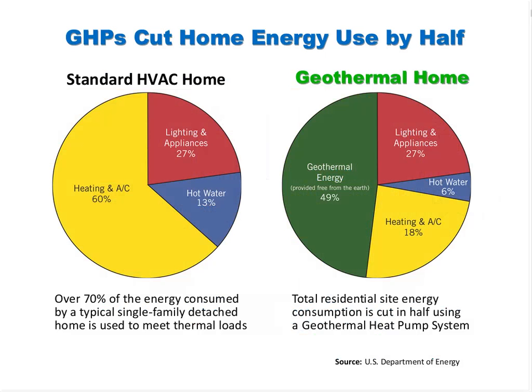And the reason's simple. It's all about ground versus air temperatures. Ground temperatures are a lot more moderate and stable than air temperatures, especially in the summertime. We're all feeling it this summer. Air temperatures can be very volatile and extreme. All you need to do is go onto the roof of a commercial building with black tar and 130, 140 degrees on that roof during the summer, and those air-to-air heat pump systems up there are really struggling to be efficient, whereas if a geothermal system's being used, it's tapping that much more moderate temperature air drawn from the earth, through the water system, through the piping system that hooks into the geothermal heat pump itself.